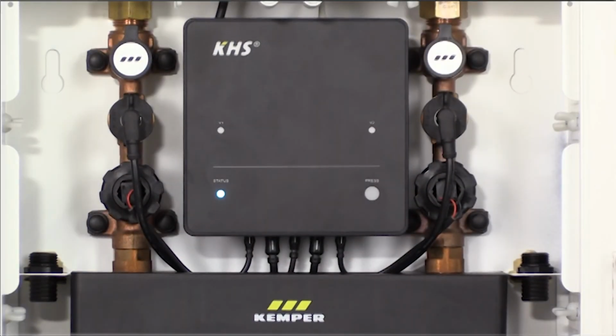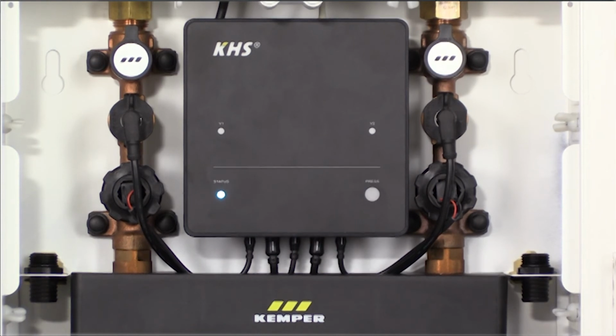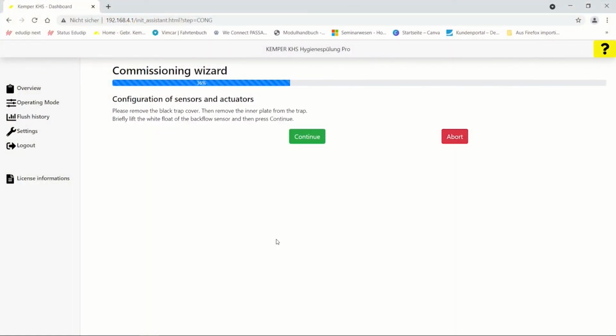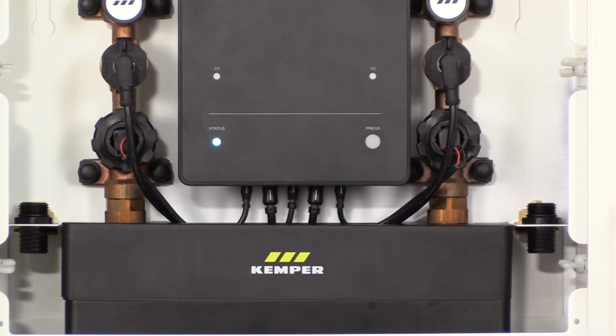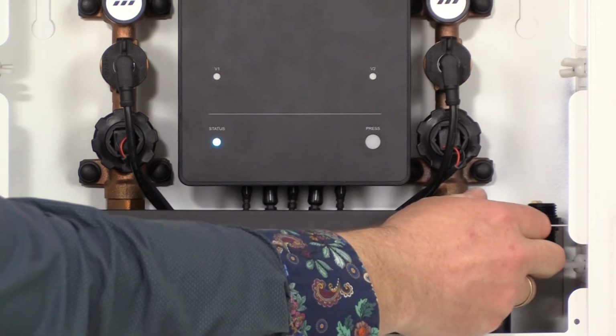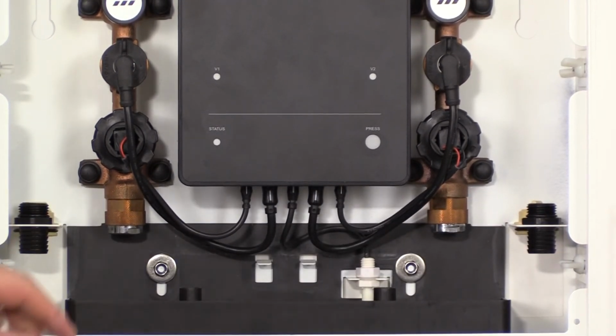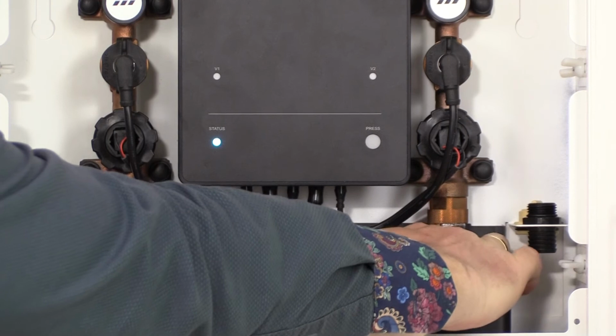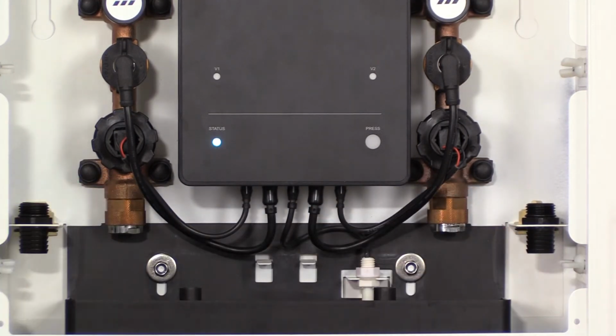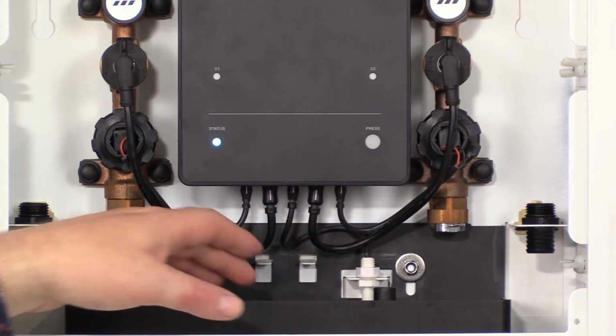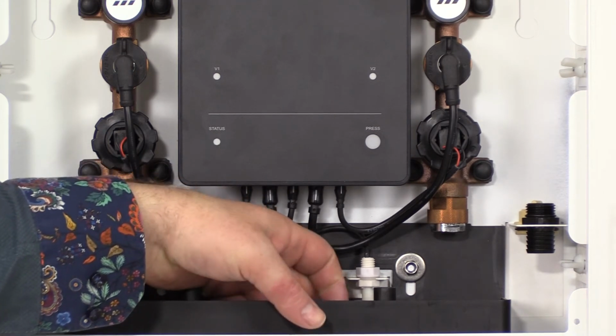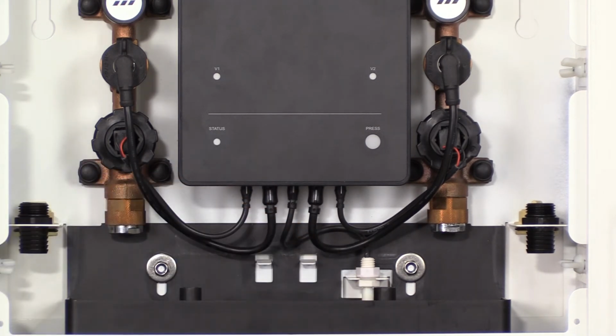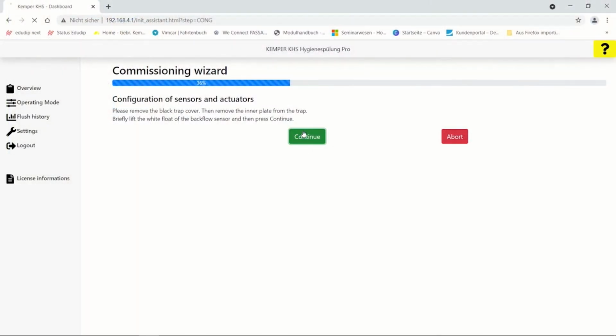Now we can hear the alarm of the hygiene flush box. If that's the case, we can confirm. Now we are checking the overflow sensor. To do so, we are removing the cover of the siphon and the metal sheet underneath it. Now we are lifting the float switch shortly and release it again. After that, we can press continue.